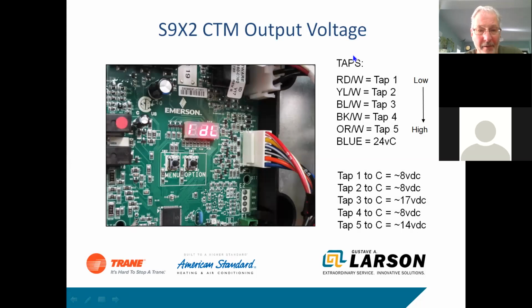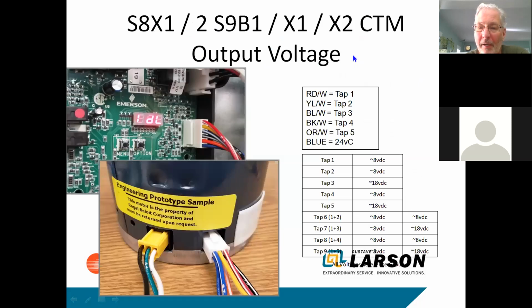And again, it's done through the menu and the option button on the furnace, and we will cover this in more detail with the furnaces, but that can all be done through there. Or if it's a 9-tap furnace, there's ways to check it. But again, you have 1 through 9, and if you get past tap 5, it actually starts to combine taps to get the proper airflow.